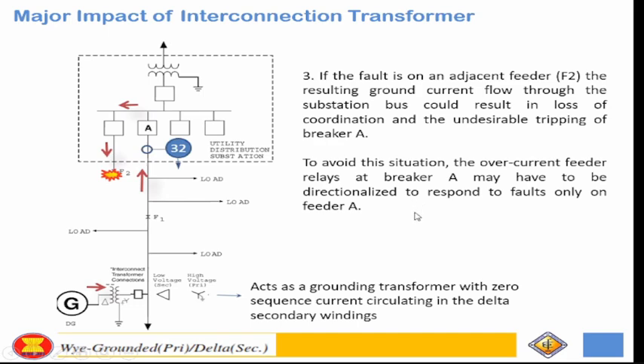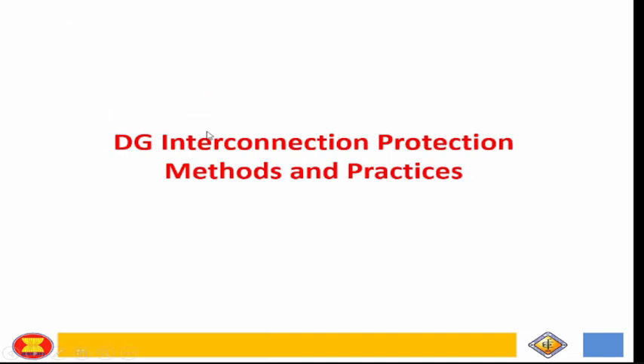So kailangan natin i-convert siya from non-directional overcurrent into directional overcurrent, no? Because this transformer here acts as a grounding transformer, with zero sequence current circulating in the delta secondary windings. Okay? So, yun yung ano niya. Mayroon siyang fault contribution, no? Or redistribution of fault current.